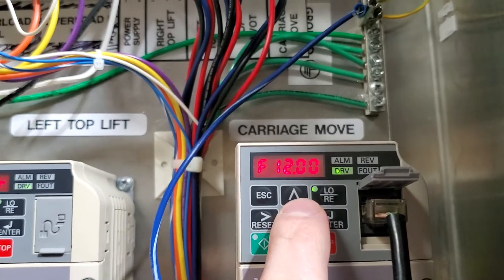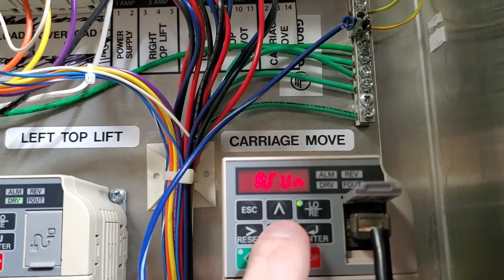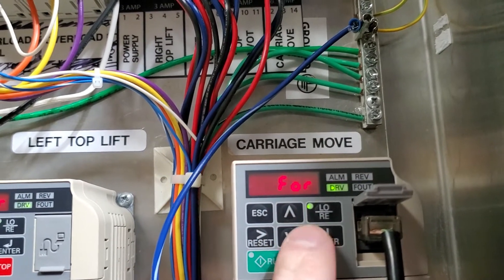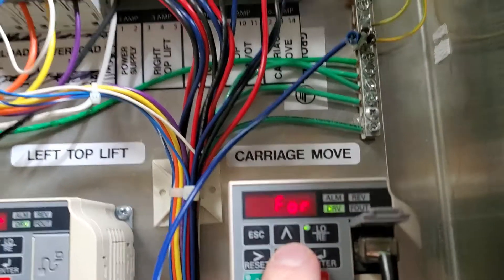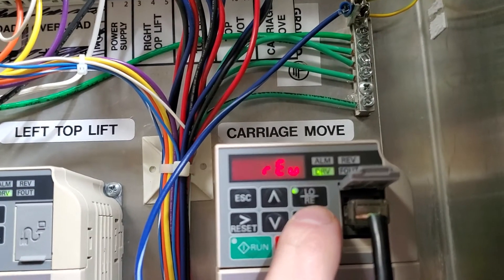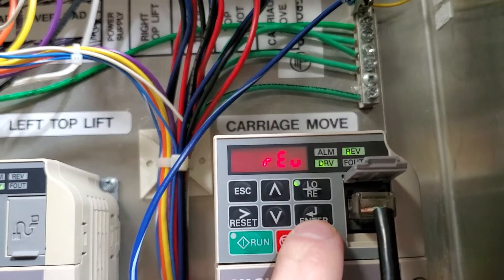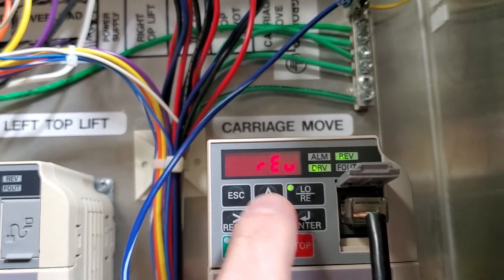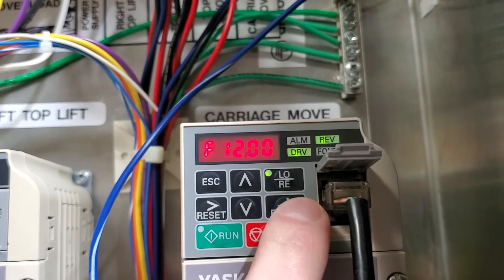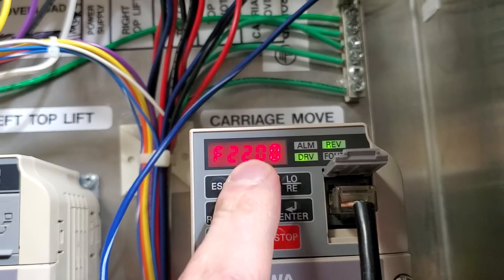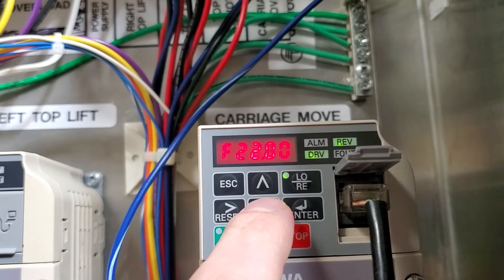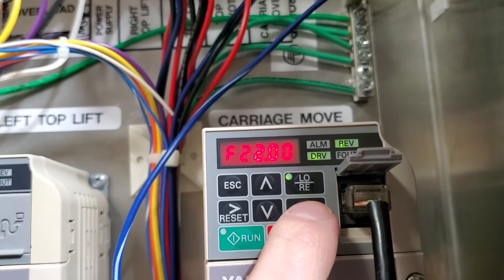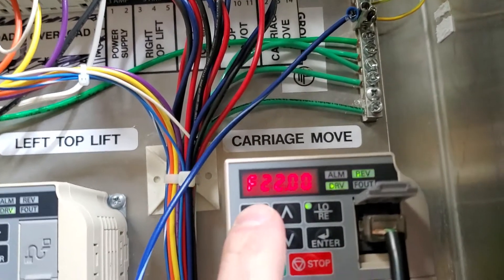You would set your frequency, use the up or down arrows to find FOR or REV, which is for forward or reverse. Then to change it, you press enter, use the arrow key, press enter again to change the frequency. You would press enter, change it to whatever you want, just do like 22 so you can see it change. Press enter, then it's still blinking - you have to hit escape to get it to not blink so you can run it.